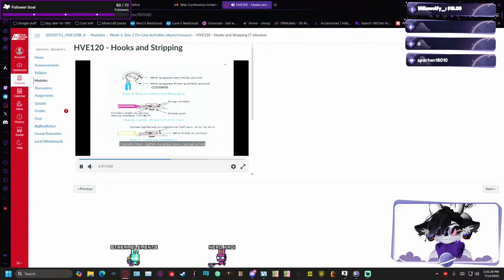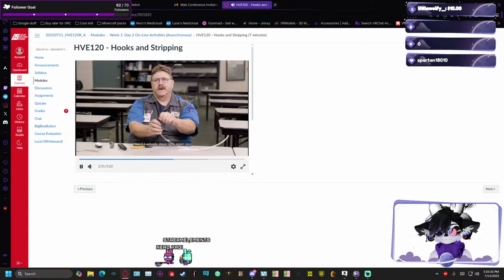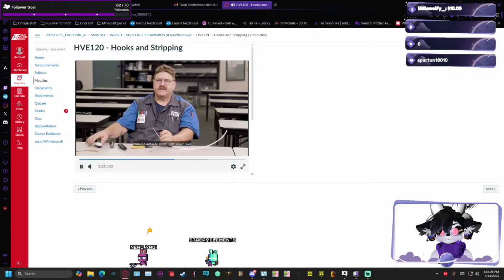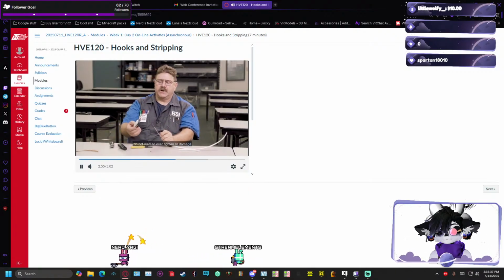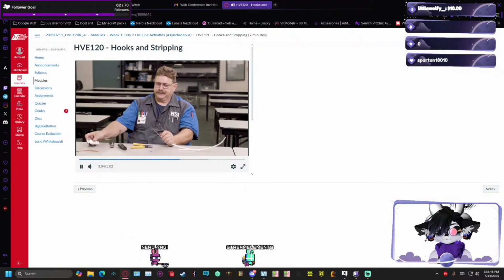Typically when I tighten my screw down, I will get a hold of the wire and give it a little movement and see if it actually stays tight. Again, you do not want to over tighten or damage your screw because it's not going to make a better connection. 12 inch-pounds is all it takes.